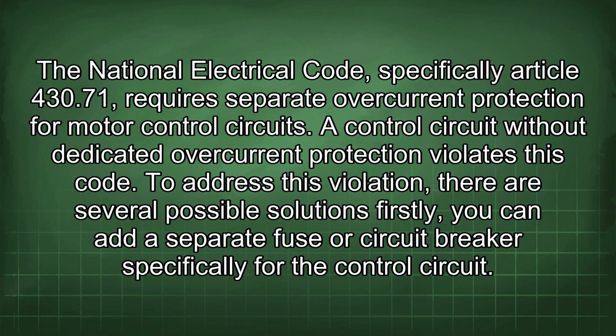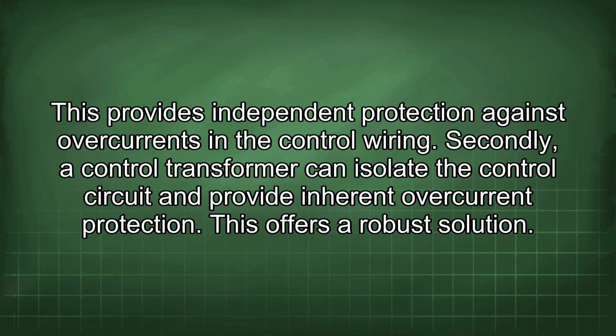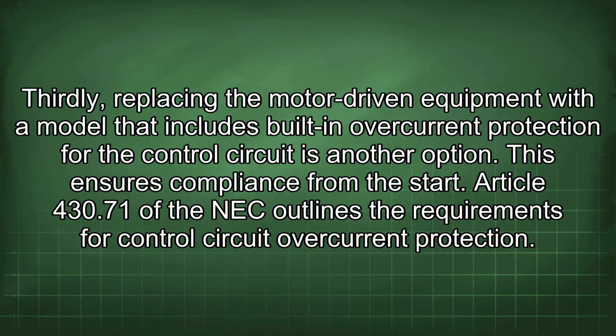Firstly, you can add a separate fuse or circuit breaker specifically for the control circuit. This provides independent protection against overcurrents in the control wiring. Secondly, a control transformer can isolate the control circuit and provide inherent overcurrent protection. This offers a robust solution. Thirdly, replacing the motor-driven equipment with a model that includes built-in overcurrent protection for the control circuit is another option. This ensures compliance from the start.